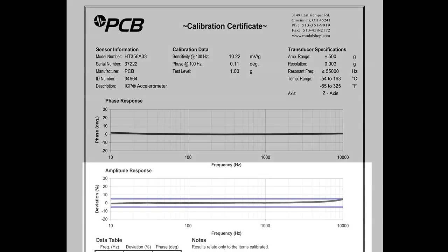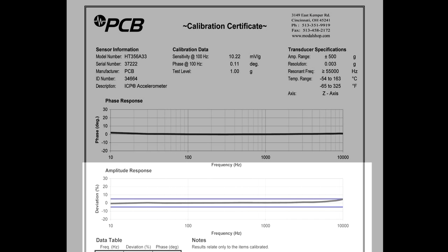Measuring the sensitivity and frequency response of an accelerometer is the most basic and common test performed on a sensor. Any change to the performance of the sensor will eventually be identified by one of these two tests.